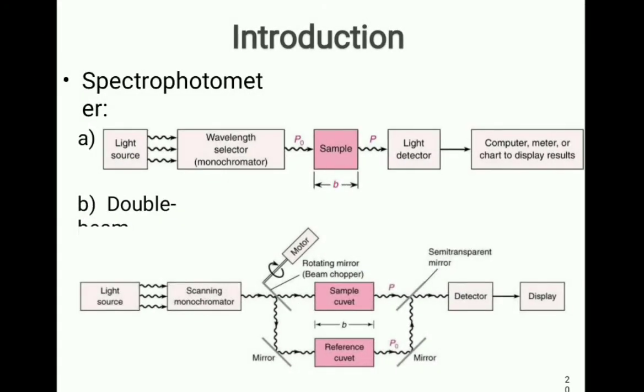In the case of double beam spectrophotometer, the difference lies in that two beams of light are generated. That means, at the same time, we can measure the absorbance of our sample and the reference.